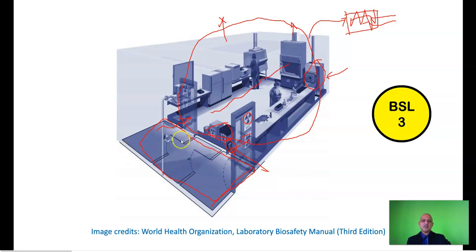This is the area in which you change, and then once you change here, you proceed to the negative pressure zone, what is known as a containment zone. So air can only enter into the zone, of course via HEPA filter, and can only exit via HEPA filter. Now if there is a drop in the pressure in this particular zone, we term it as a breach of containment, and we put into place specific protocols to limit the release of the pathogen. This is a basic BSL3 facility.